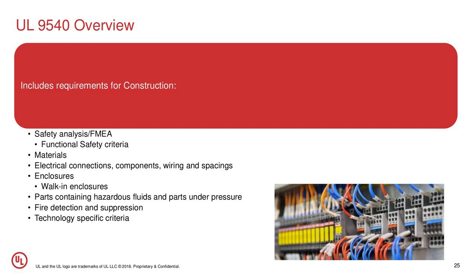We have material requirements and enclosure requirements, including for walk-in enclosures, because these could be very large systems built into containers that someone may walk into temporarily to do servicing. So we have to consider—they're not completely a building, but there are things that have to be considered for the safety of workers dealing with them, as well as any parts containing hazardous fluids or under pressure.